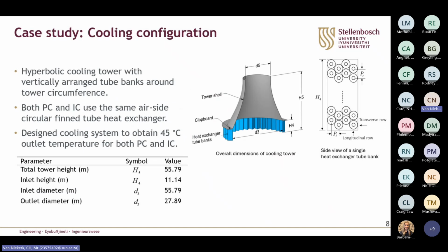The cooling tower we used consists of a hyperbolically shaped cooling tower with vertically arranged heat exchanger tube banks around the circumference of the cooling tower. Here, we employ a circular fin tube heat exchanger where both the pre-cooler and intercooler use this airside configuration. So during the design phase of the project, which I won't be covering in this presentation, the tower had to reject the cycle heat load to achieve an outlet temperature of 45 degrees Celsius for both heat exchangers. And just to explore a bit of a larger design space, we completed a parametric study varying some key geometric features. And at the end of the day, we ended up with a 55-meter high tower.